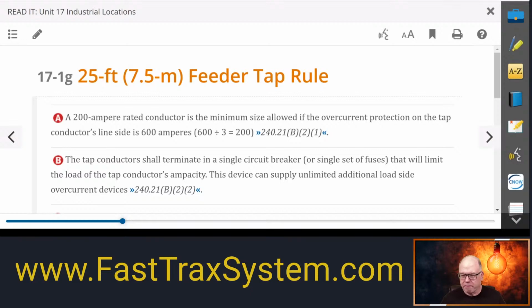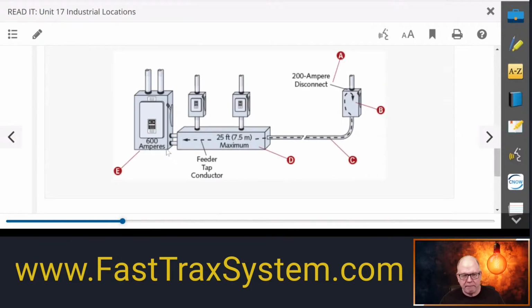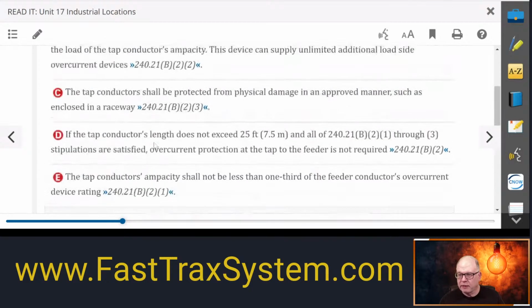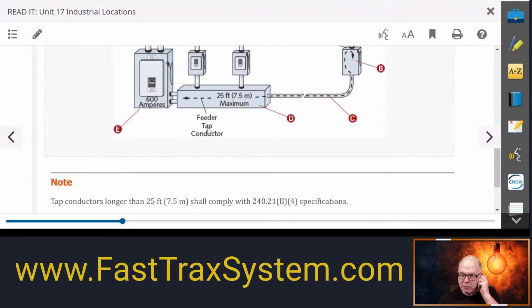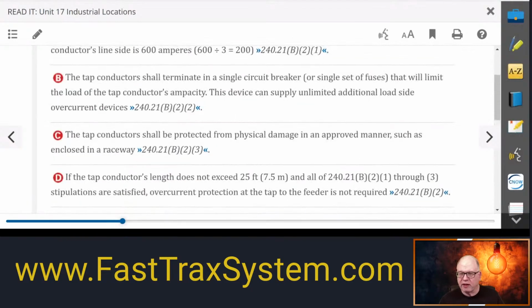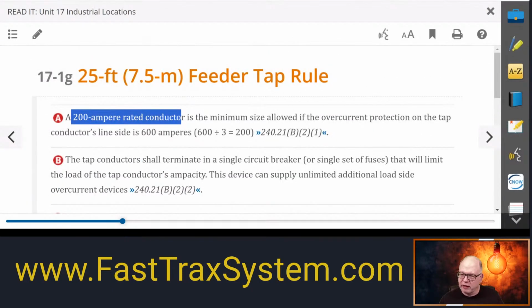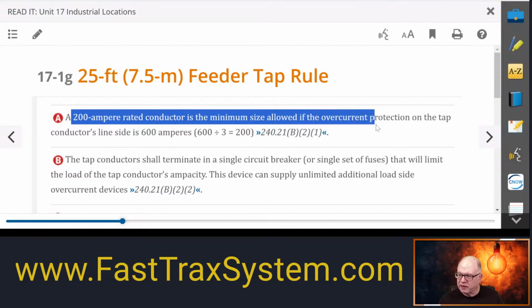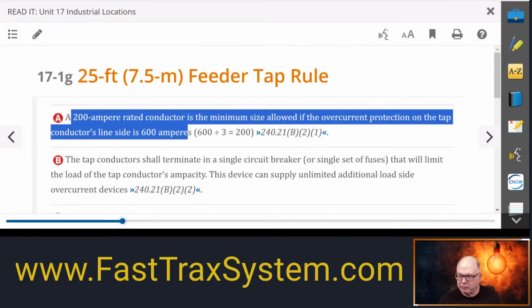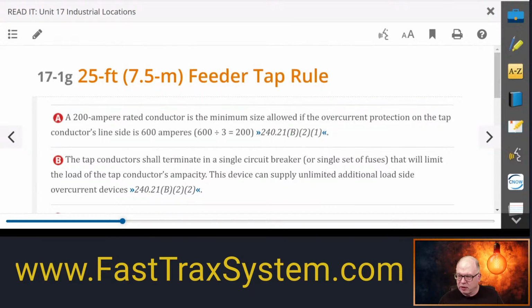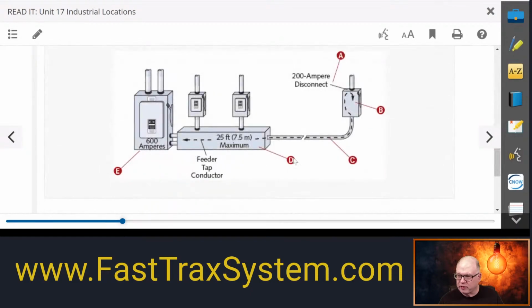All right, so in this case, here's the 200 amp right here, and it's tapping a 600 amp ahead of it, right? So this is 200 amp, 600 amp ahead of it. We want to use the tap rules here. Okay, so it says a 200 amp rated conductor is the minimum size allowed if the overcurrent protection of the tap conductor's line side is 600 amps. Okay, so that is 240.21(B)(2). We'll look at it. So this conductor here looks to me like it has to be, since it's terminating into a 200 amp device, and we know we can't use the next size up rule, right?